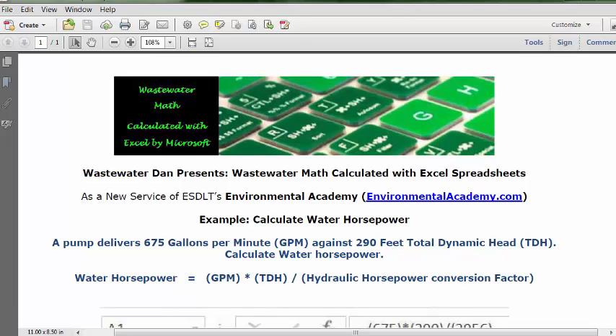Today's problem reads: a pump delivers 675 gallons per minute (GPM) against 290 feet total dynamic head (TDH). Calculate water horsepower.